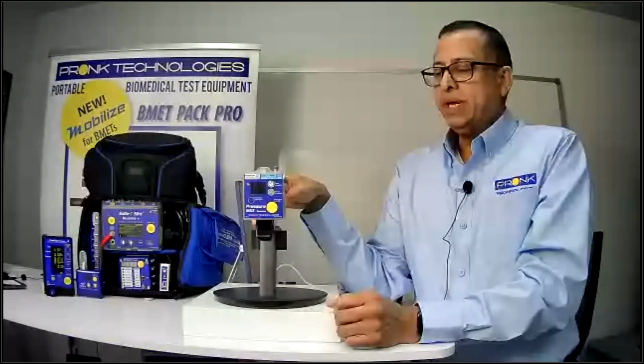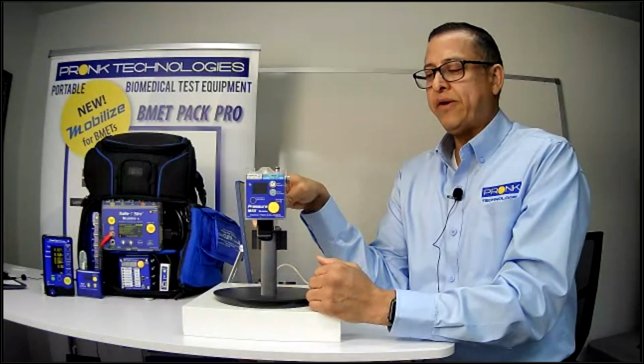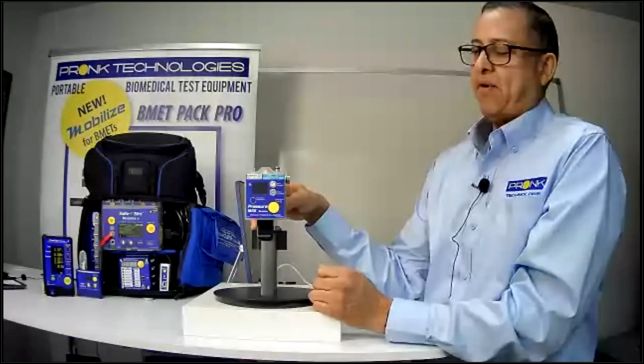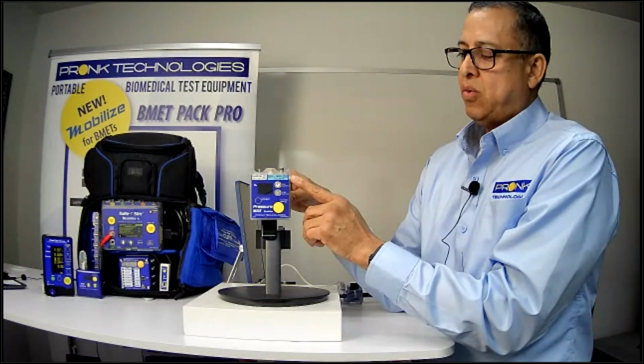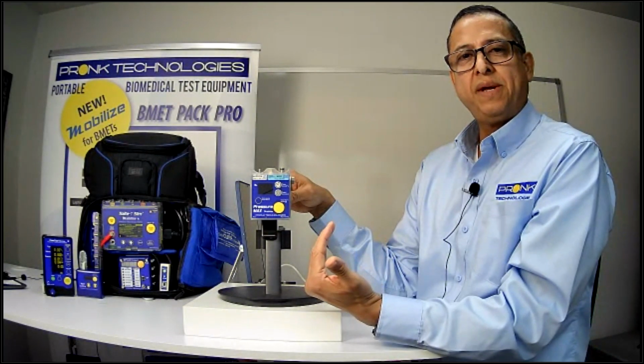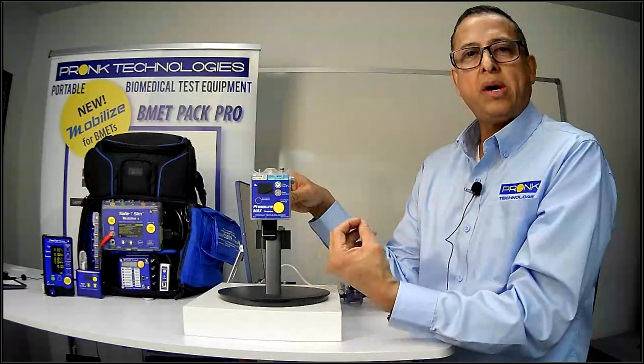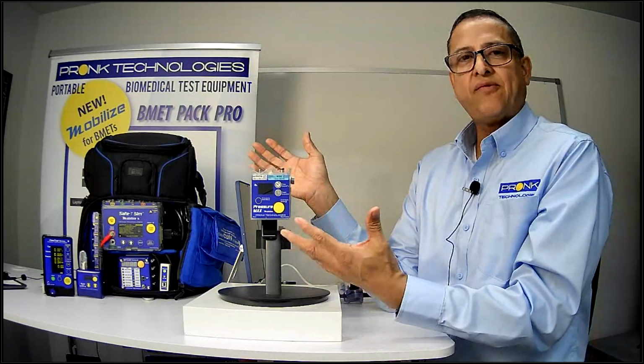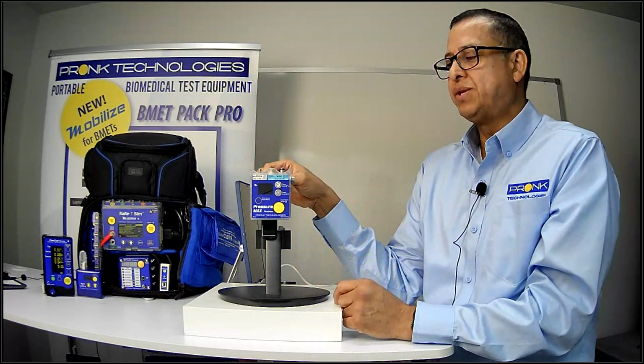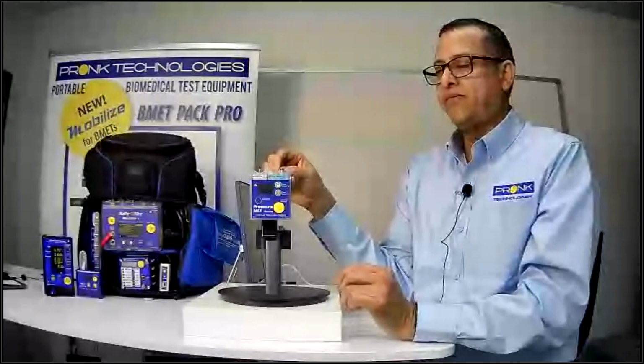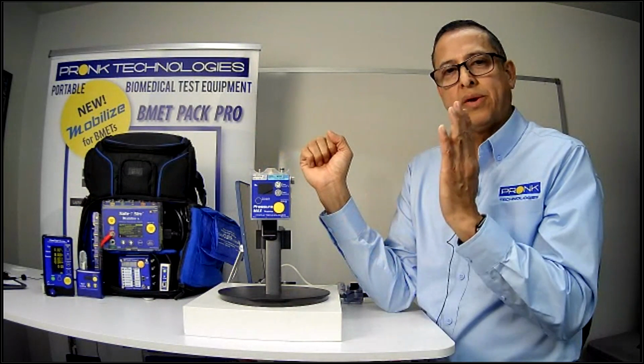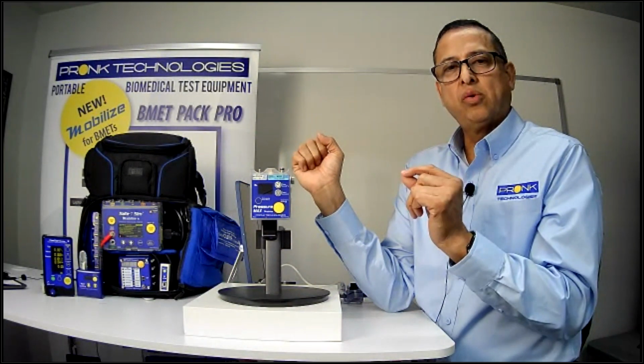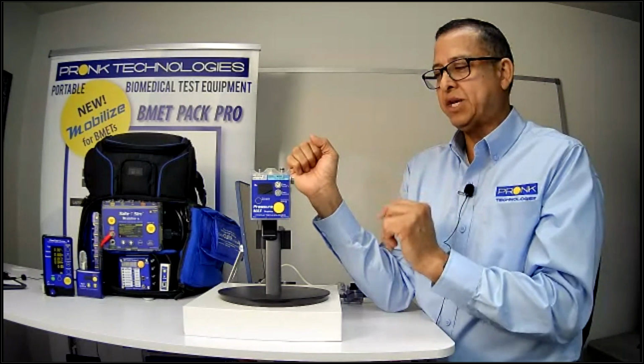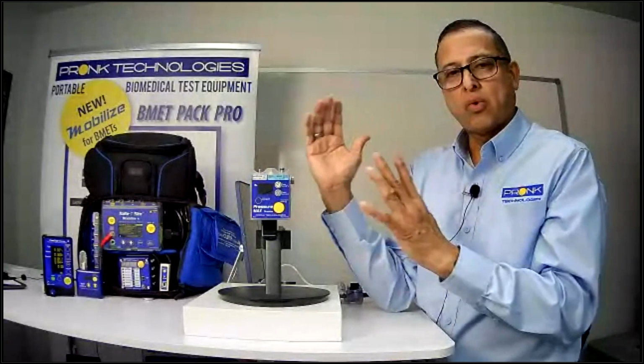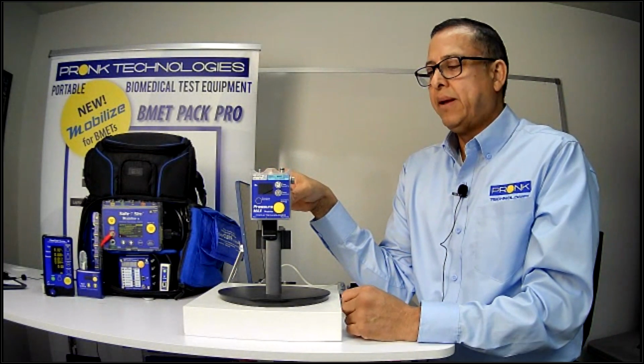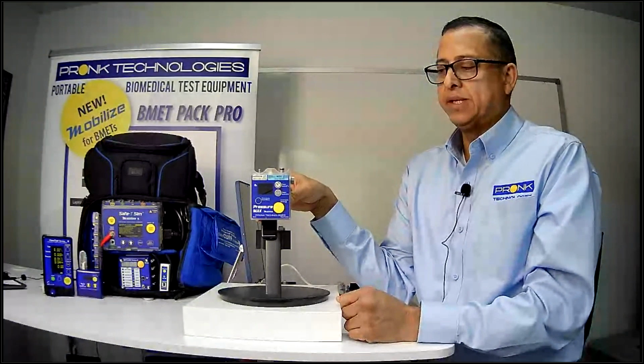The 2 different ports have different capabilities. You have the wide port here, which is able to measure from -14 psi all the way up to 100 psi, but you're not going to sacrifice accuracy. The unit provides up to a 1% accuracy for all of the readings. So it doesn't matter what your test point is, your result will be within 1% of that test point you're testing at. So great range, and you're able to get very precise readings on that port.